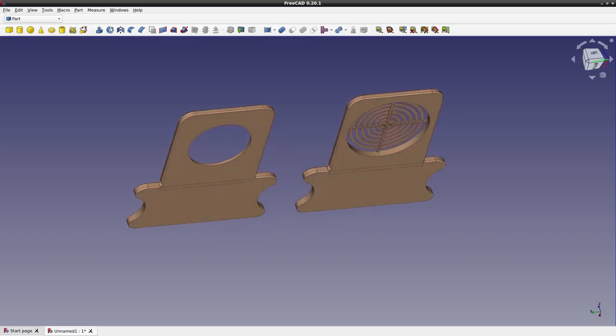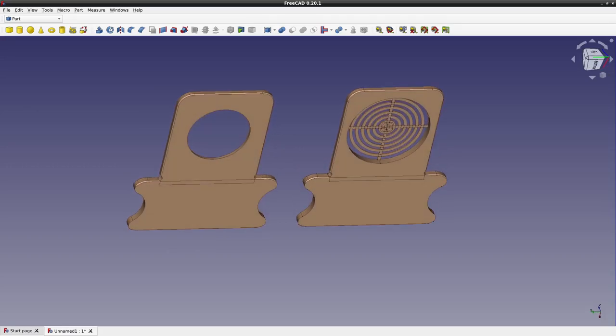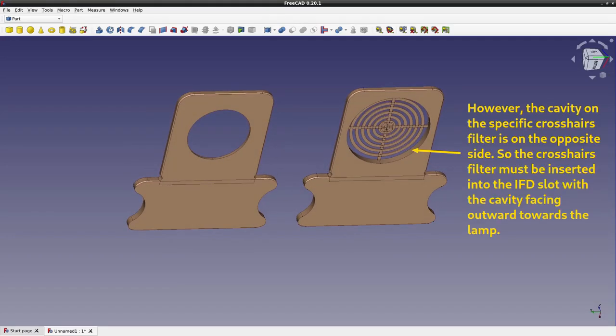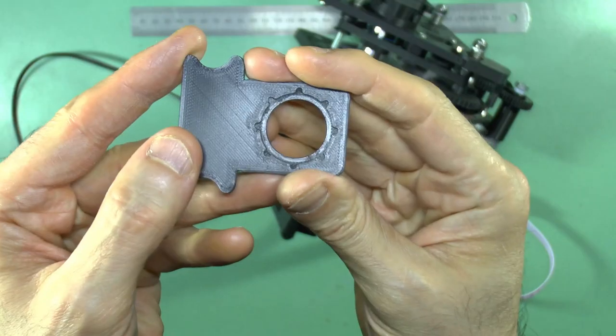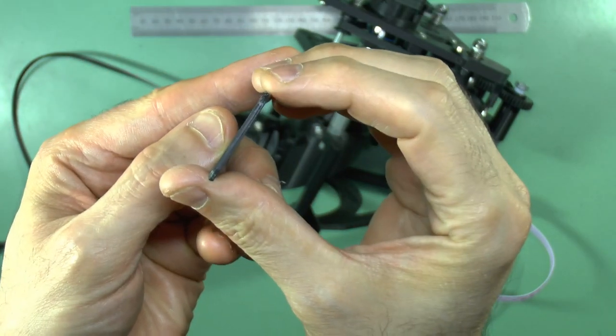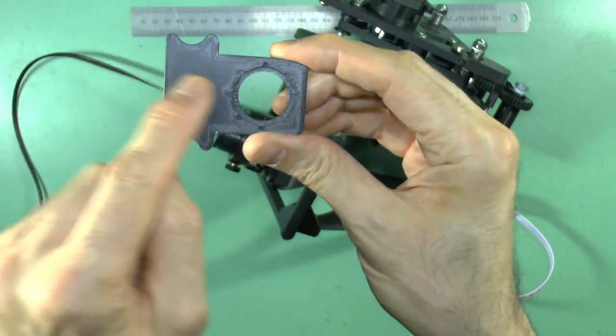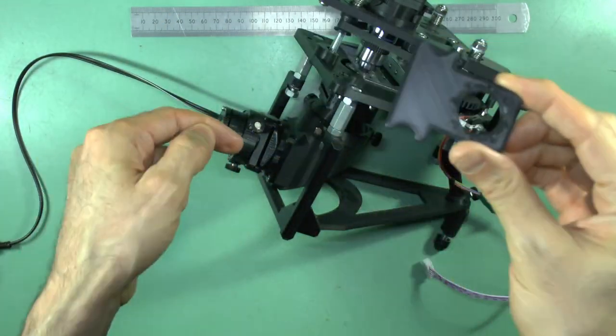That is, with the filter cavity on the same side as the chamfer on the edge. So, for all IFD filters other than the all-in-one crosshairs filter, you must insert them with the filter cavity facing inwards towards the mirror block.